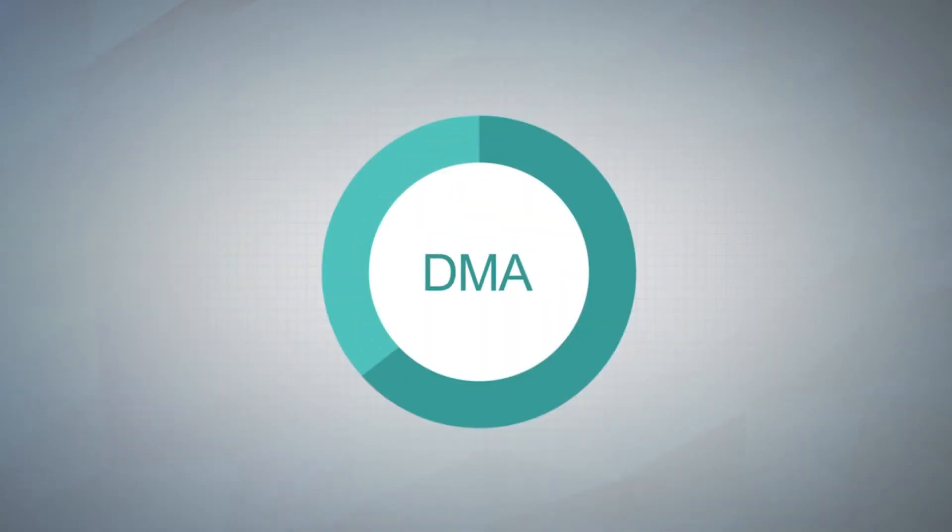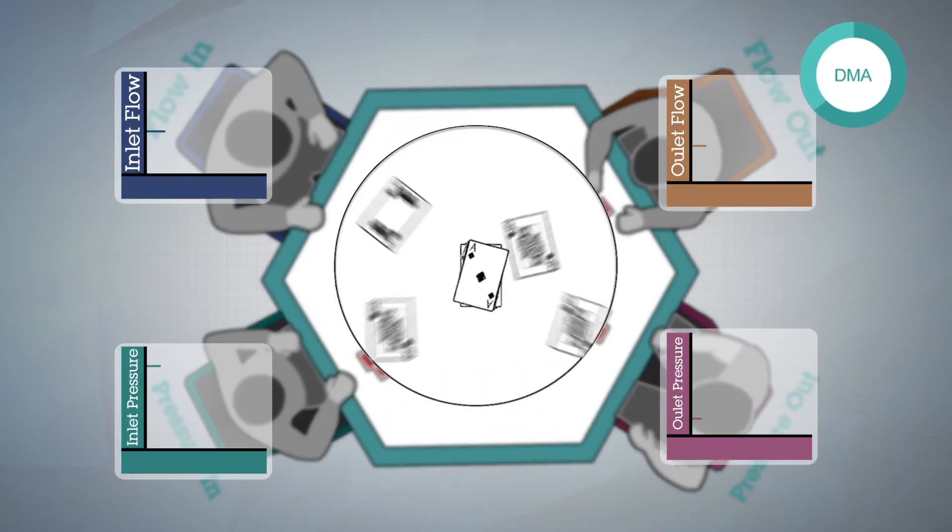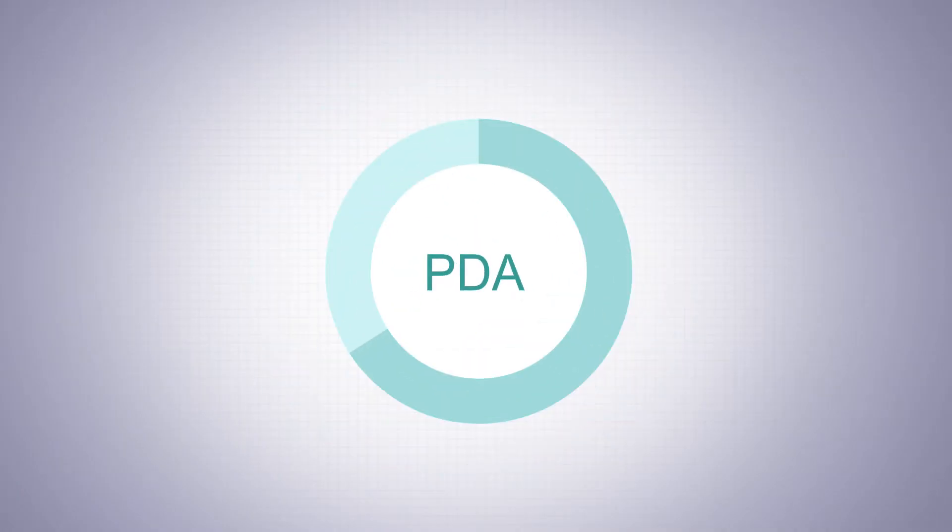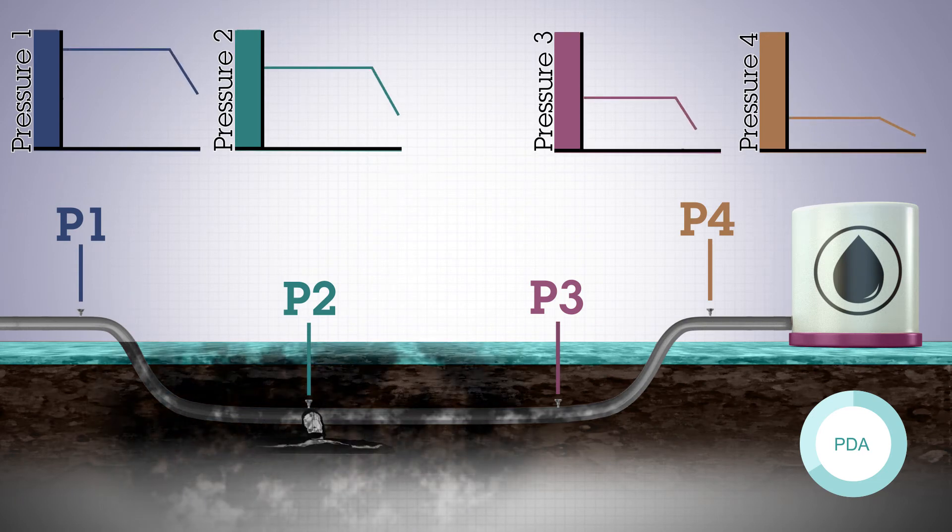The DMA algorithm monitors flows, pressures, and other signals along the pipeline for the unique combination of signals that only occurs with a rupture. The Pressure Difference Analysis algorithm compares pressures along the pipeline to detect ruptures on all areas of a pipeline.